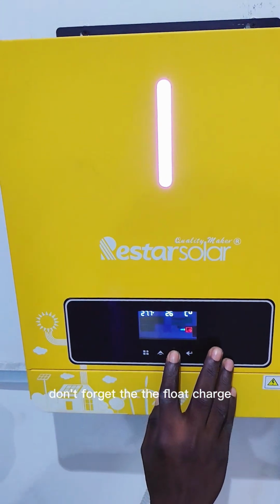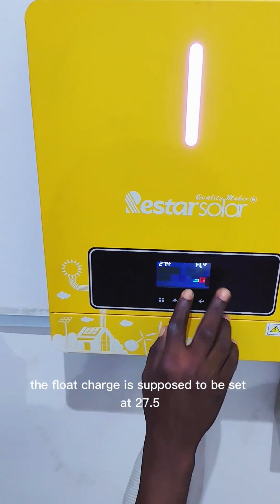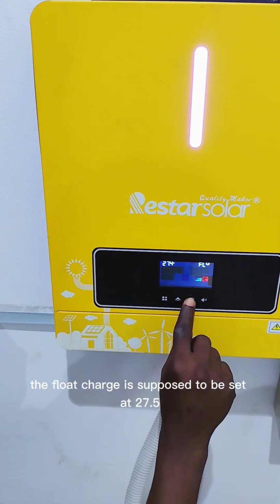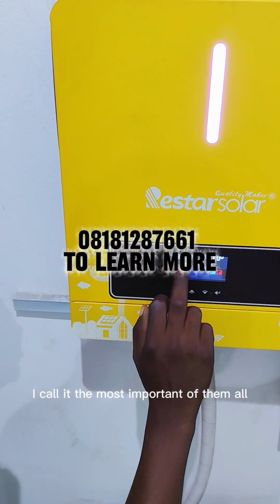Don't forget the float charge. The bulk charge is to be set at 27.8. The float charge is supposed to be set at 27.5, and the cutoff voltage, which I called the most important of them all, should be at 24 volts.